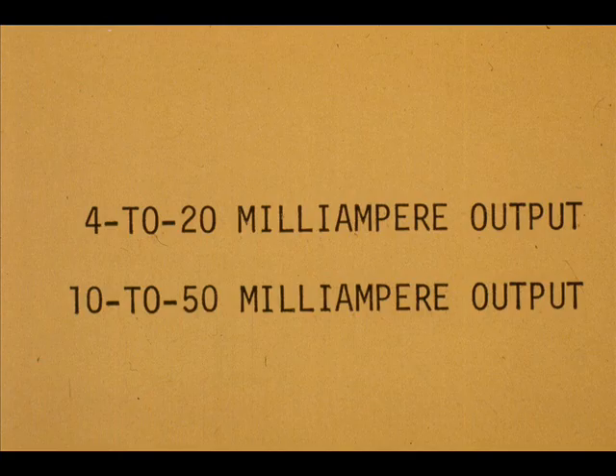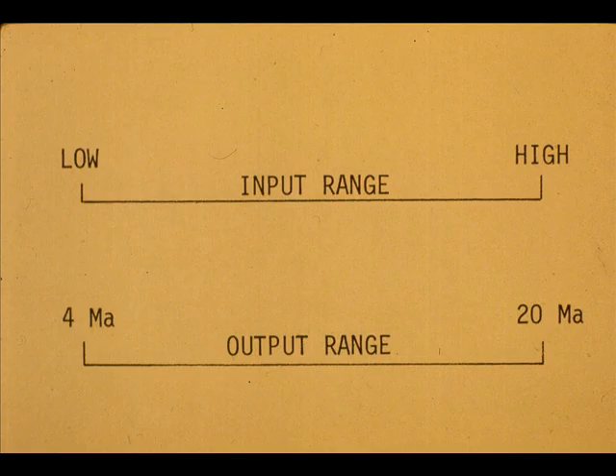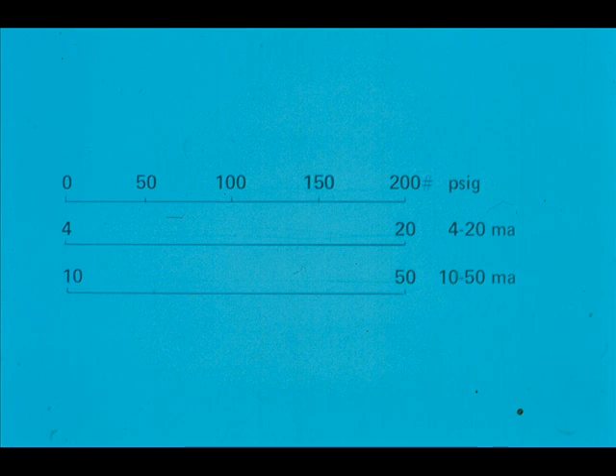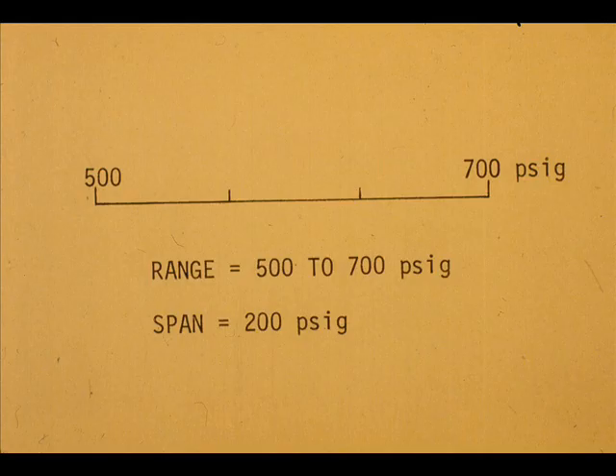Our two transmitter output ranges give two fixed reference points for any input range. For the 4 to 20 milliamp output, 4 milliamps represents the low end of the input range and 20 milliamps represents the high end. Similarly, for the 10 to 50 output signal, 10 milliamperes represents the low end of the input range and 50 milliamps represents the high end. For a zero to 200 pound pressure transmitter, we have these known calibration points for the two output ranges.